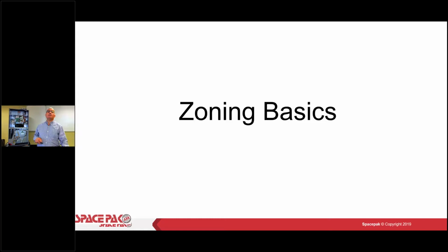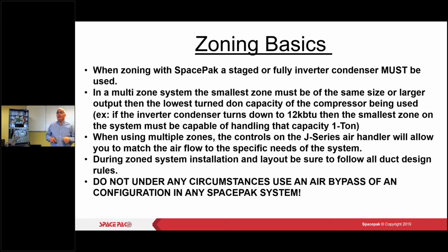All right, so zoning. We can zone with SpacePak. We can zone in our plenum with our dampers, or we can actually have a damper per 2-inch outlet if you choose to do that. If you're doing anything with zone dampers, you must have at least a 2-stage outdoor unit. Your outdoor unit must be at least 2 stages. And as you can see here, do not under any circumstances use an air bypass of any configuration in the SpacePak system.